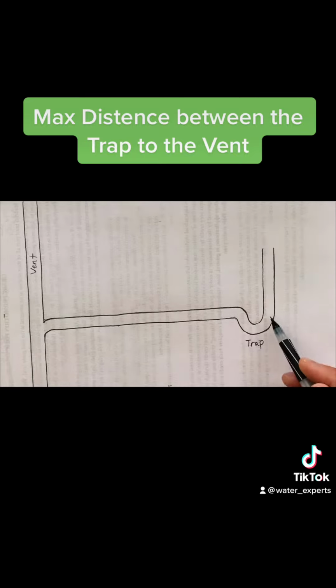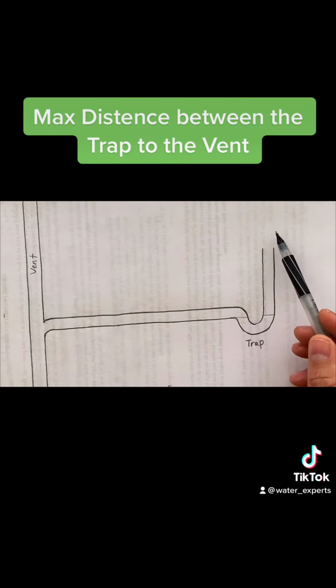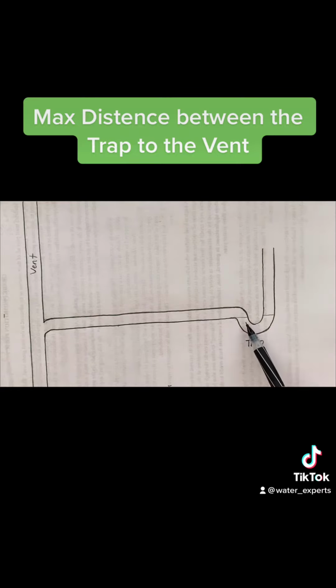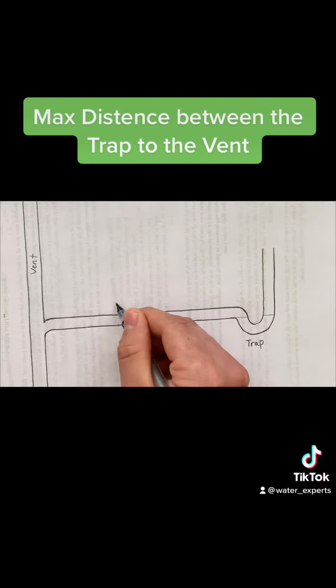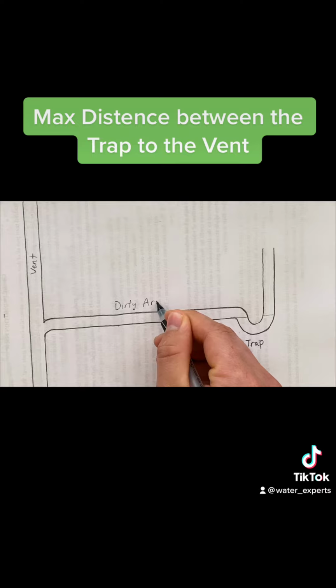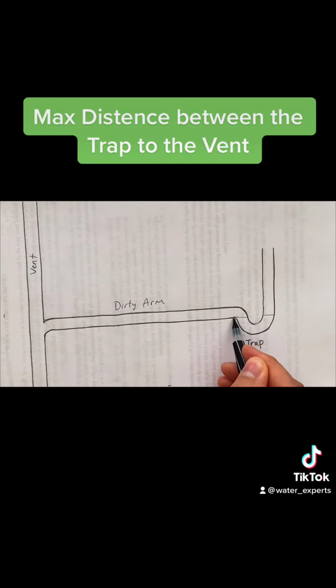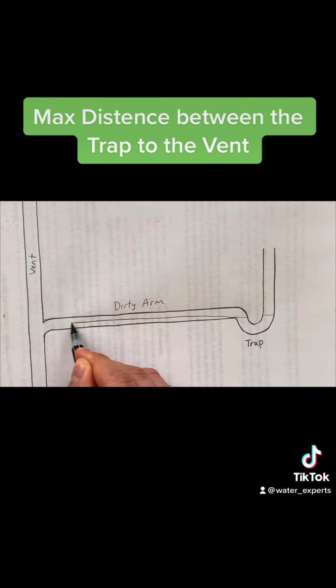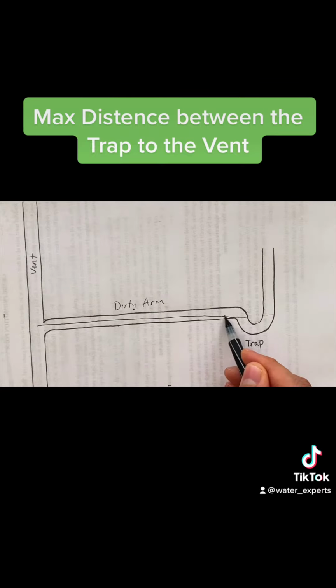So when water flows into the trap, it settles at this height. Now, when water is flowing into the drain at its maximum capacity, we're going to have a significant amount of water flowing through this dirty arm, is what it's called. And when the water flows, it is going to fill this drain at the same level of the trap. Now, what we're trying to do is allow there to be air from the vent to flow into this dirty arm, which prevents the water in the trap from siphoning out.